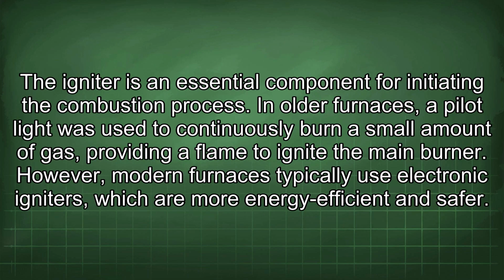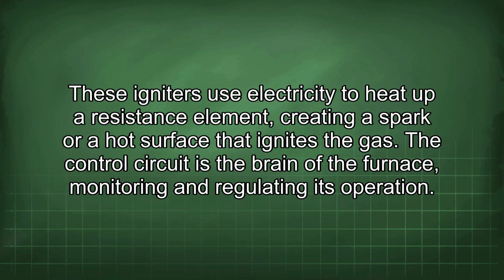The ignitor is an essential component for initiating the combustion process. In older furnaces, a pilot light was used to continuously burn a small amount of gas, providing a flame to ignite the main burner. However, modern furnaces typically use electronic ignitors, which are more energy efficient and safer. These ignitors use electricity to heat up a resistance element, creating a spark or a hot surface that ignites the gas. The control circuit is the brain of the furnace, monitoring and regulating its operation.